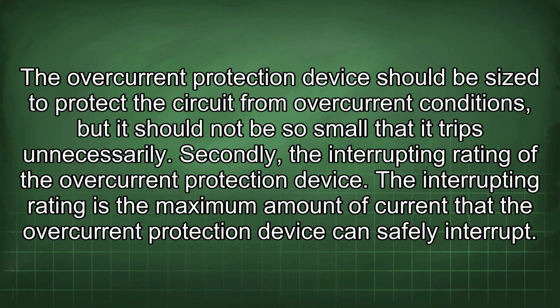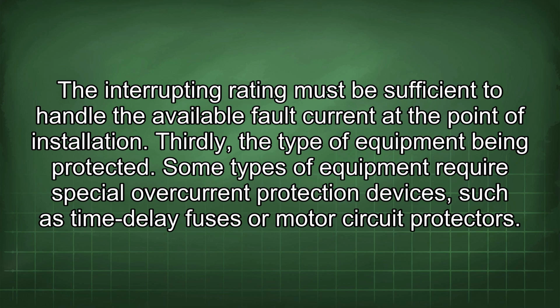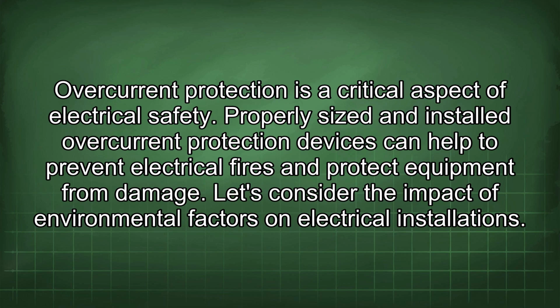Secondly, the interrupting rating of the overcurrent protection device. The interrupting rating is the maximum amount of current that the overcurrent protection device can safely interrupt. The interrupting rating must be sufficient to handle the available fault current at the point of installation. Thirdly, the type of equipment being protected. Some types of equipment require special overcurrent protection devices, such as time delay fuses or motor circuit protectors. Overcurrent protection is a critical aspect of electrical safety. Properly sized and installed overcurrent protection devices can help to prevent electrical fires and protect equipment from damage.